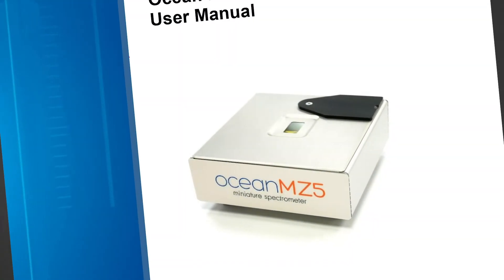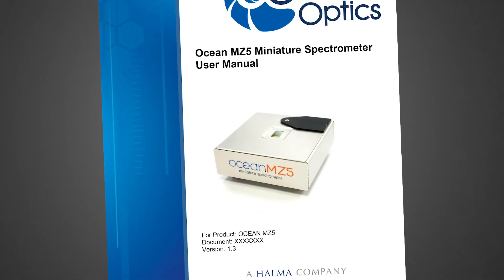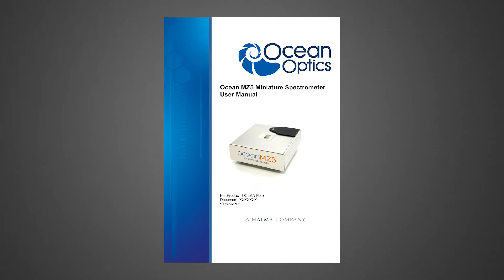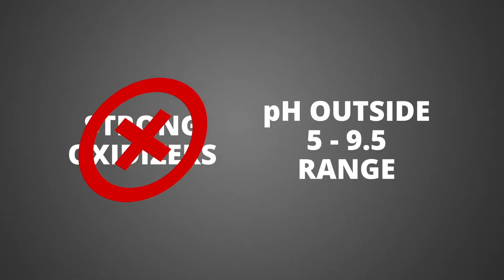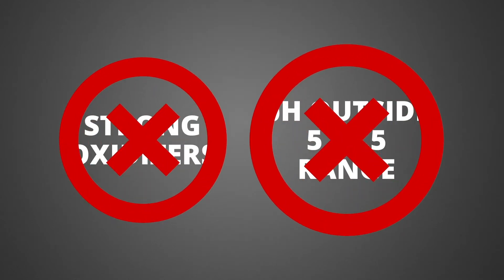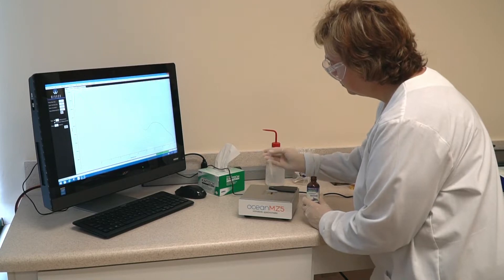Before making measurements with your MZ5, you'll want to check out the user's guide to confirm that your liquid samples are compatible with the zinc selenide crystal. For example, the MZ5 should not be used with strong oxidizers or acids and bases with a pH outside the 5 to 9.5 range. Make sure to review this information before applying any samples to the zinc selenide crystal surface.